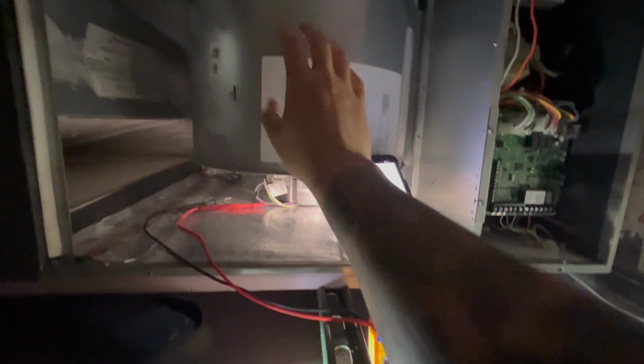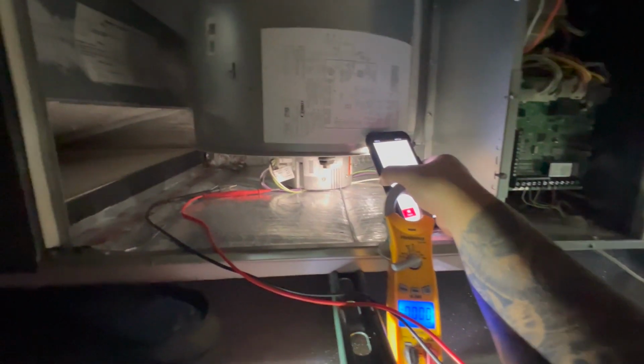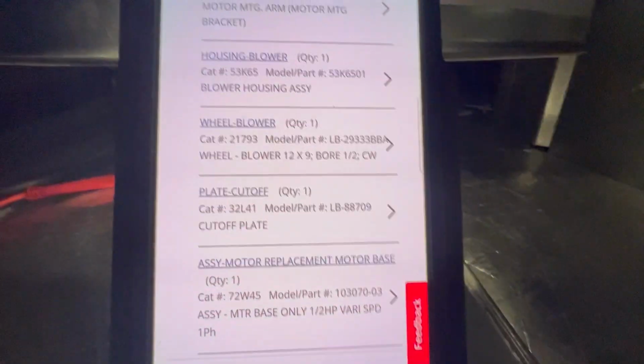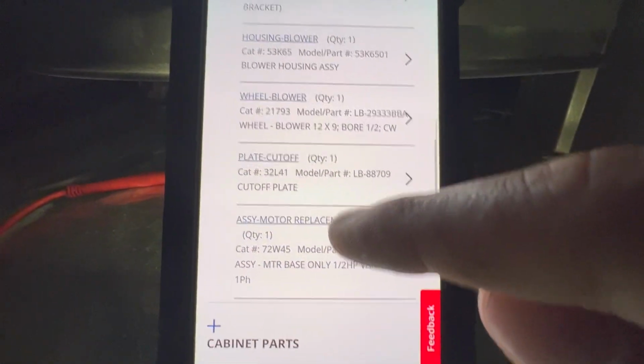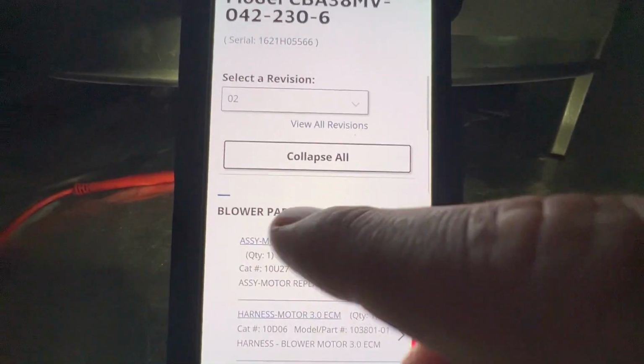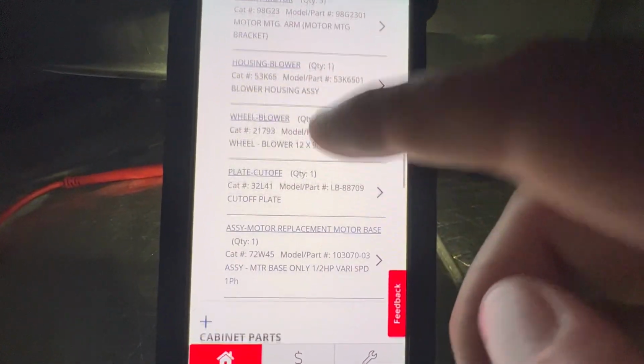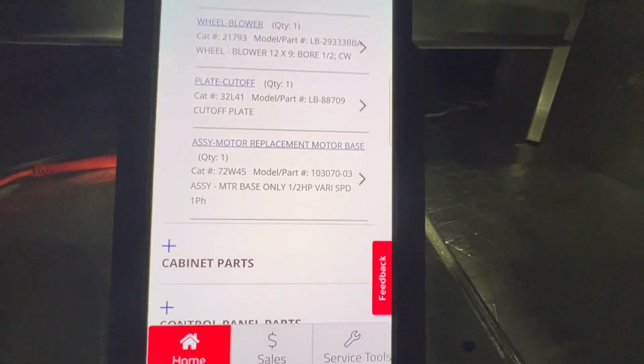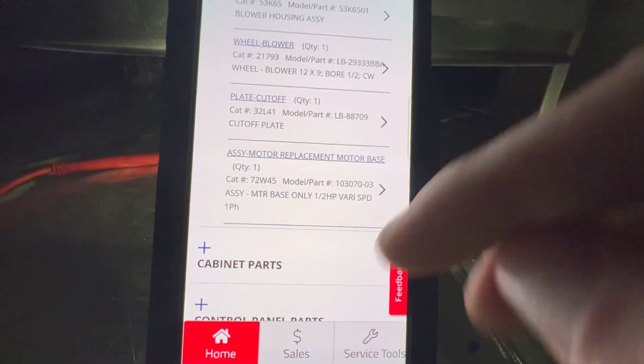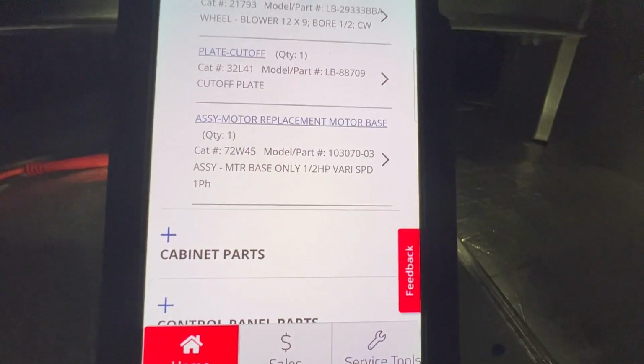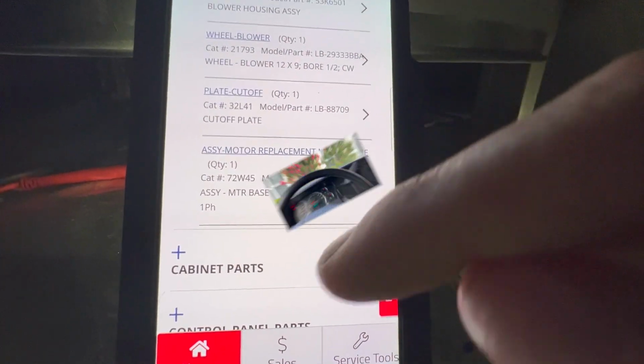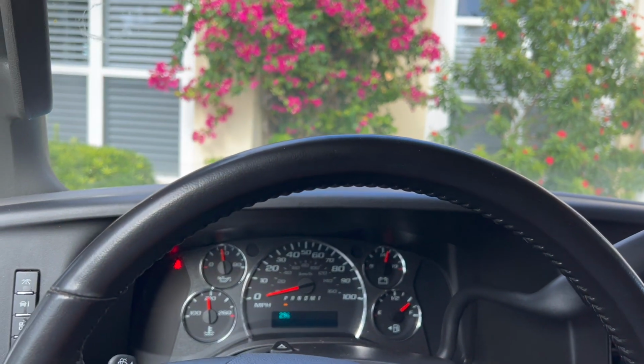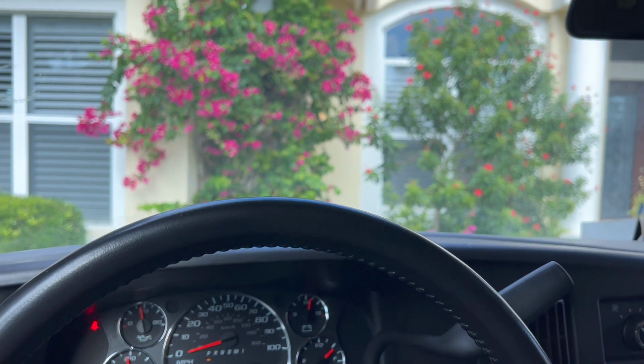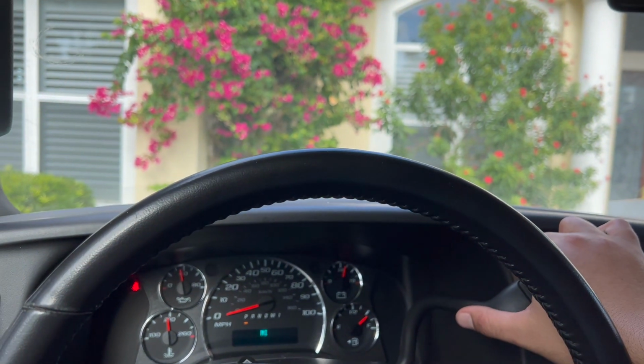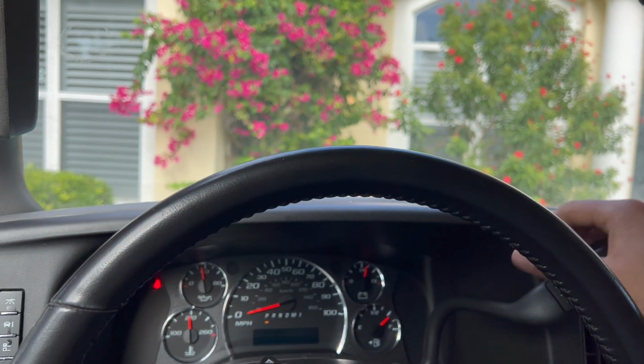In this case, this is gonna be a bad blower motor. On the Lennox app, I went into the blower parts just to make sure, because we do have blower motors on our trucks, but I want to make sure we have that kind. So we need a 72W45. They had the blower motor at a warehouse close by, so we're gonna go get it and get it installed. Yep.